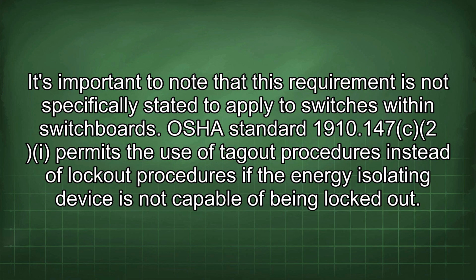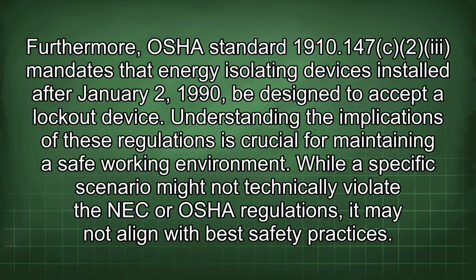OSHA Standard 1910.147 permits the use of tagout procedures instead of lockout procedures if the energy isolating device is not capable of being locked out. Furthermore, OSHA Standard 1910.147 mandates that energy isolating devices installed after January 2, 1990 be designed to accept a lockout device. Understanding the implications of these regulations is crucial for maintaining a safe working environment.